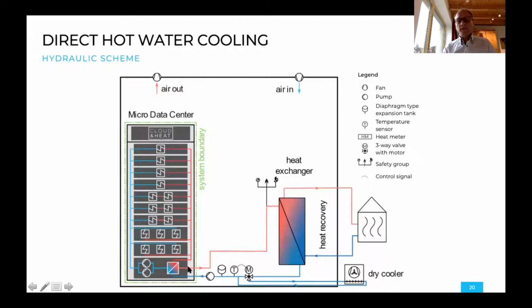And this heat now can be extracted, and it can go now to the building. It goes to a buffer tank, for example, and this buffer tank can be hooked up to the floor heating or to the warm water supply of the building. And if this buffer tank is fully filled because the heat is not needed in the building, this warm water comes back here. And if it's too hot, basically you switch this motor, and then the hot water goes outside to a dry cooler in a closed loop circuit, and the hot water is then cooled down to a level that's acceptable for the servers.